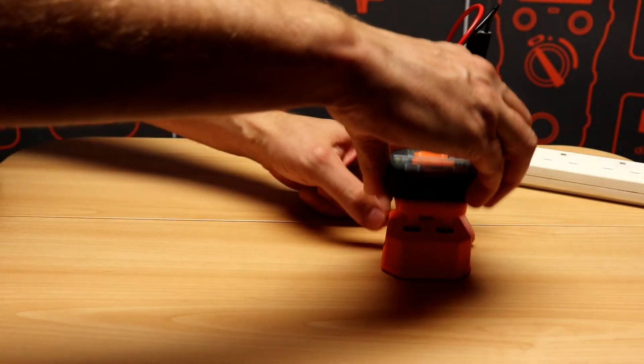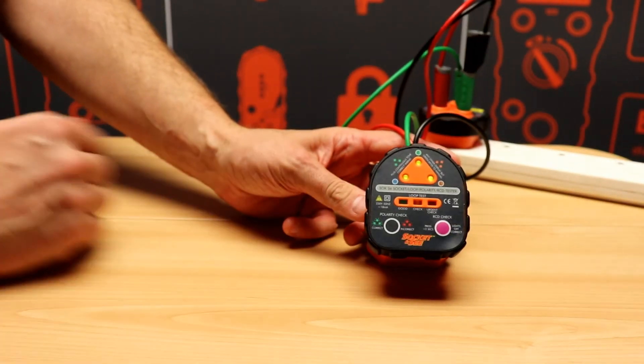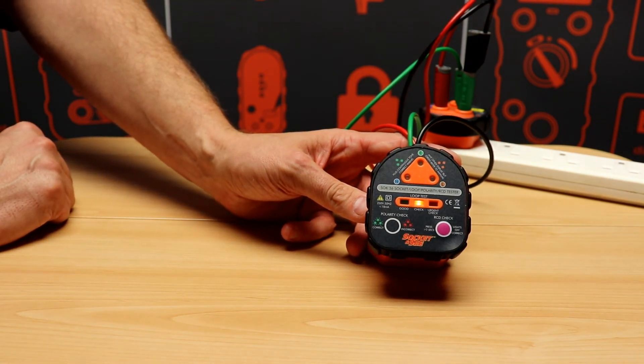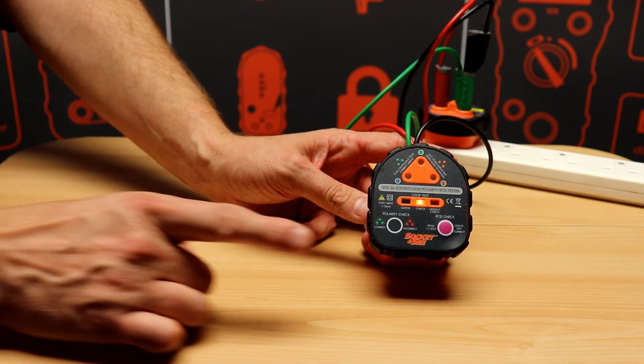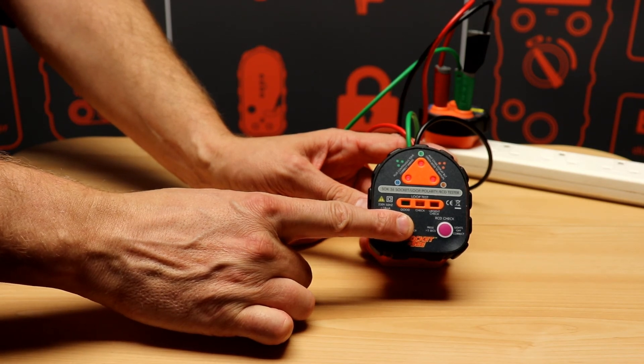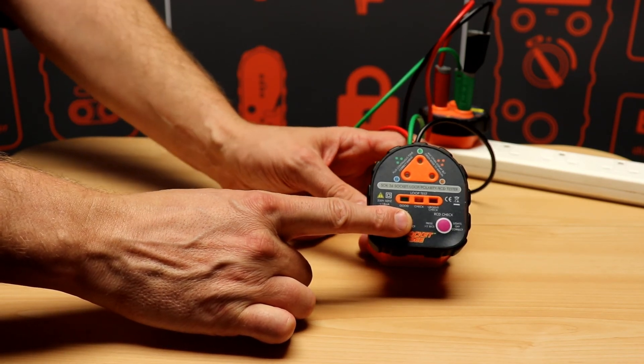If I simply plug the socket tester in, a socket test will be done and then an earth loop test will be done. Most socket testers won't be able to see this fault condition. But once there's a reference to earth from the Socket & See, a clear fault indication where the warbling tone is indicated.